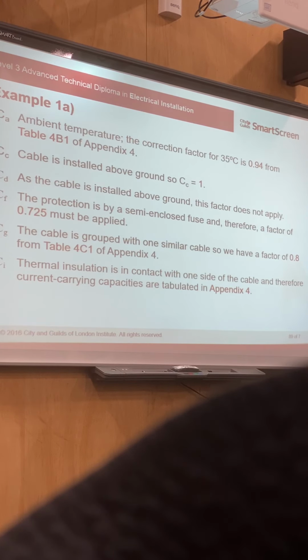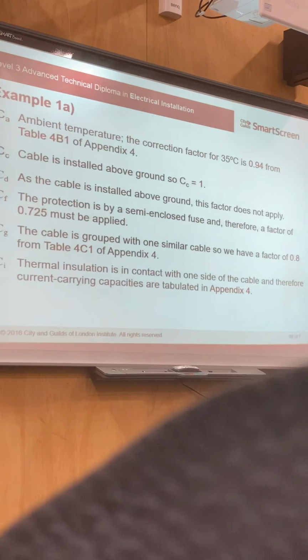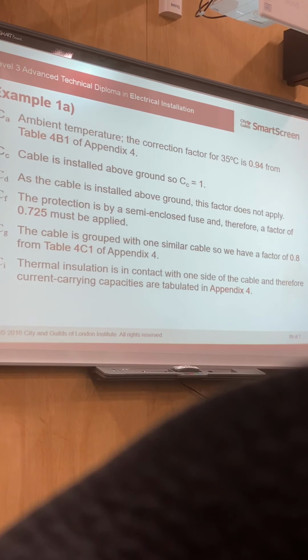Okay, so how much insulation is this going to be affected by? 100 mil, because of the depth of the joist. Okay, what's the factor that I'm going to be using off of this? 0.78.